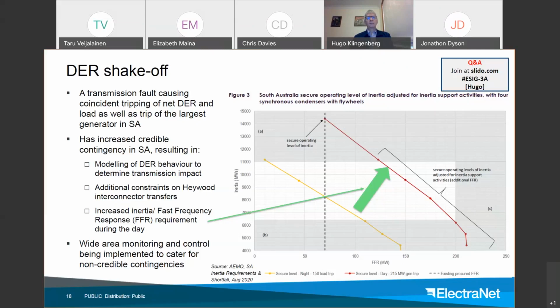risk of DER shake-off, that has an impact now on how much inertia is required in South Australia for secure system operation. And this graph here indicates that under nighttime conditions, we don't have that exposure. You have a certain amount of inertia or fast frequency response required. However, under daytime conditions, that requirement is significantly higher. And that's a direct consequence of managing for that risk that basically you need to cater for a bigger credible contingency on the network. This then over time, the last couple of years, has also indicated that we need additional emergency control schemes in South Australia.